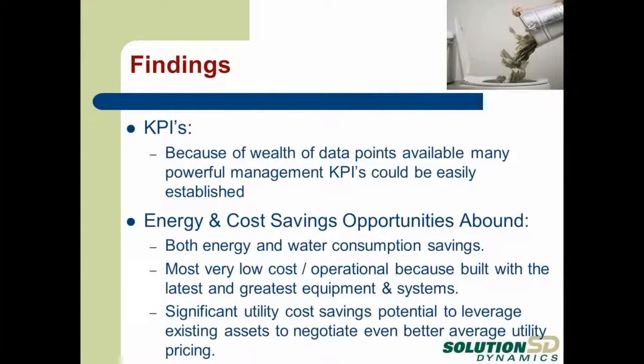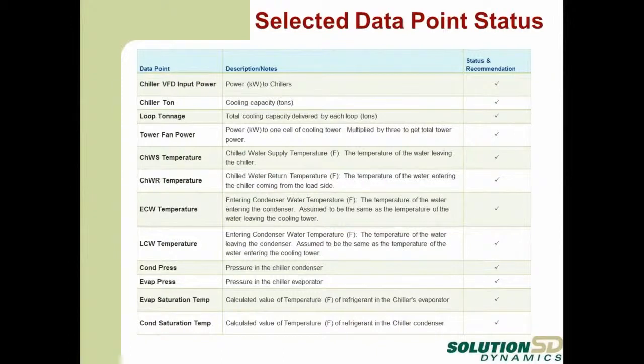I've got to buy it expensively, sometimes I can buy it cheaper. So if the facility is actually able to manage their load profile a little better, they can manage when electricity is being consumed, change that load profile, give that adjusted load profile to the electric company who's giving them this special rate, and then they can reprice the deal and actually get them an even better rate. It could be a rate where price varies throughout the day, or it could be a rate that's just been levelized to account for this revised and agreed upon load profile.